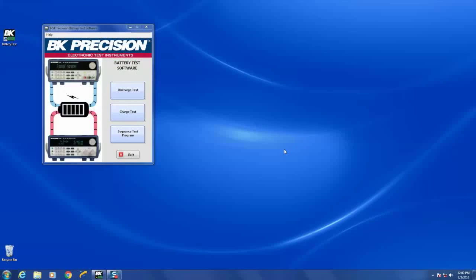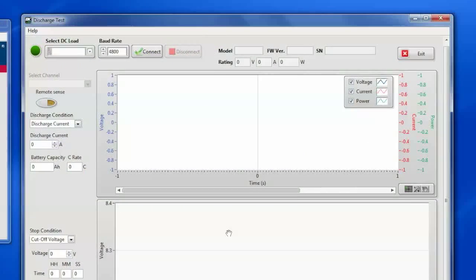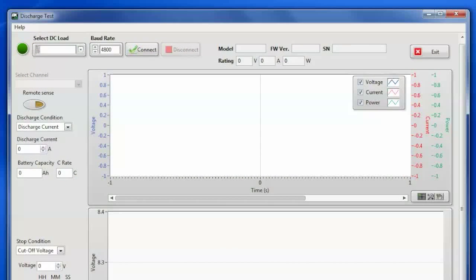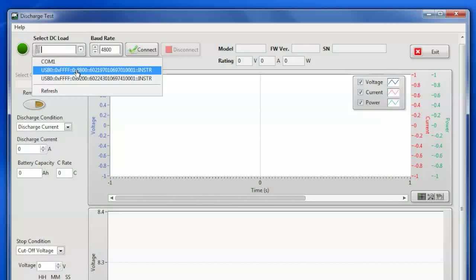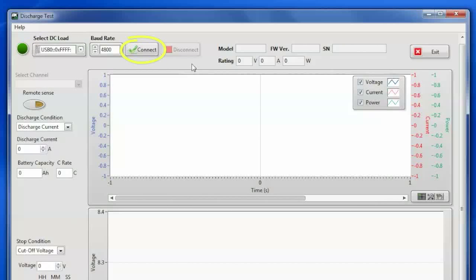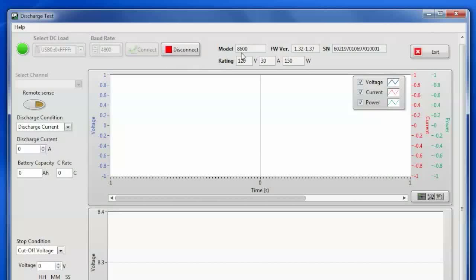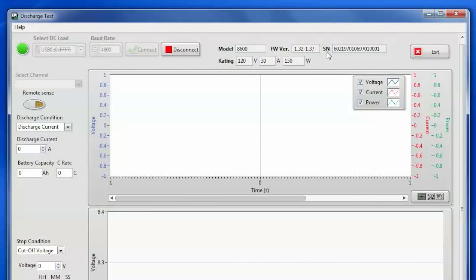Now that we've charged up our battery using the charge test, now we will do a discharge test where we'll use the load to measure the amp hour capacity of the battery. I opened up discharge test and now I'm going to find the load that's connected to the USB port and click connect. So you'll see we found a model 8600 with a firmware, serial number, all of the ratings for that DC load.